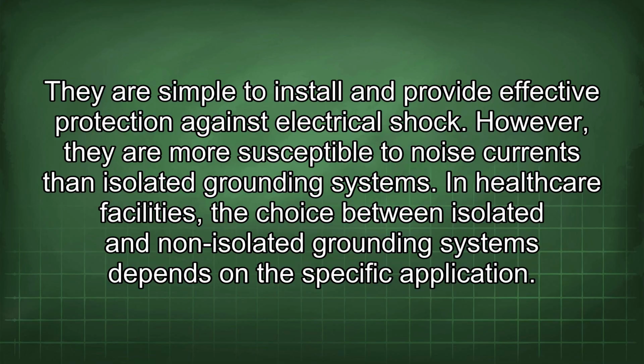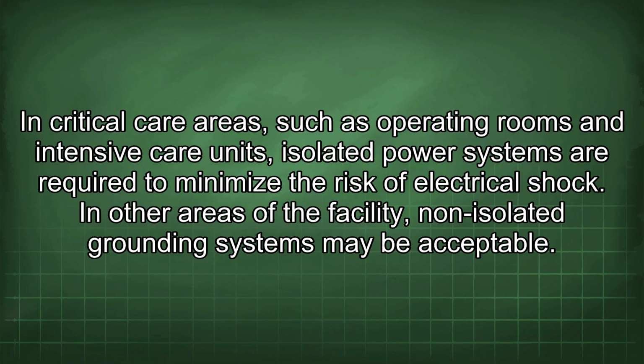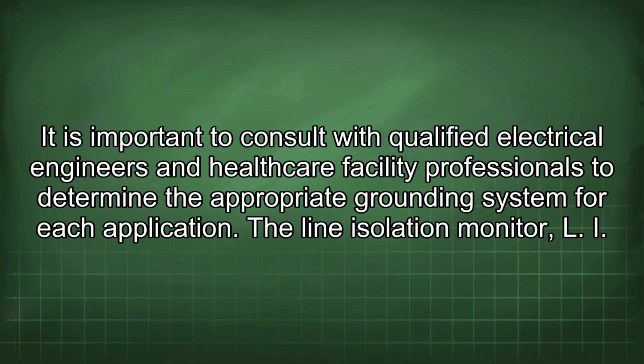In healthcare facilities, the choice between isolated and non-isolated grounding systems depends on the specific application. In critical care areas, such as operating rooms and intensive care units, isolated power systems are required to minimize the risk of electrical shock. In other areas of the facility, non-isolated grounding systems may be acceptable.